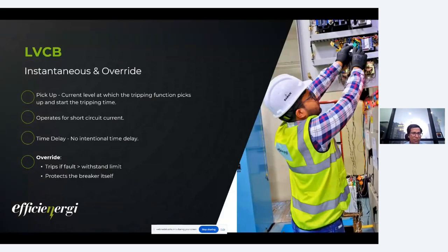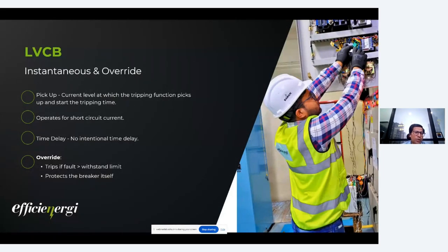The next one, again the same thing applies to the short time region also. In short time we also have the definite time feature, so there we can have a fixed time irrespective of the current magnitude. There is no relationship of inverse proportionality. This is basically required for coordination, for selectivity. Then we have the instantaneous and overrides. Instantaneous, as the name suggests, is instantaneous. Once the pickup is achieved, the current level at which the tripping function picks up, tripping is initiated immediately with no intentional delay.